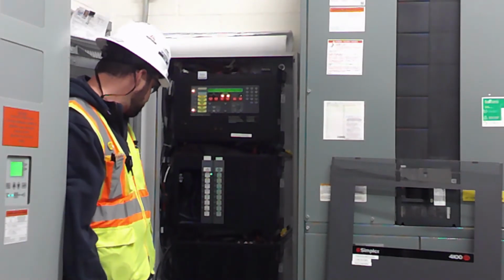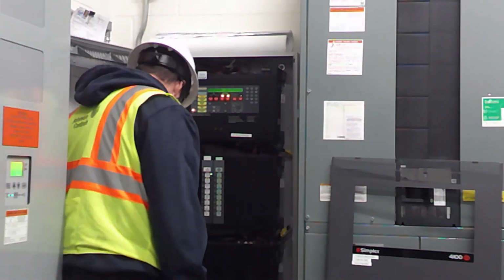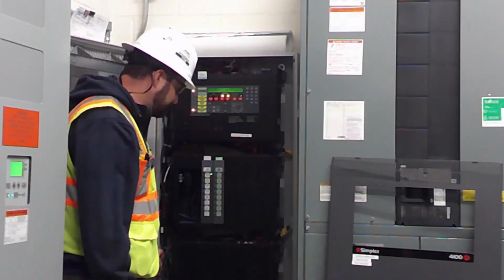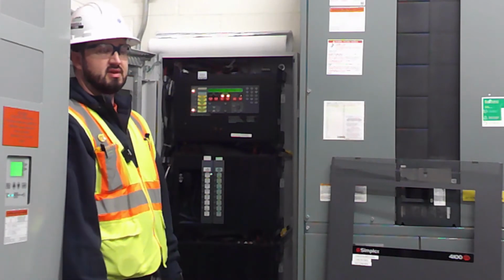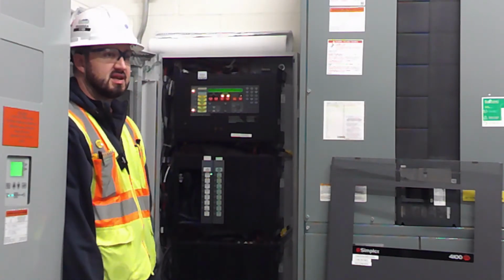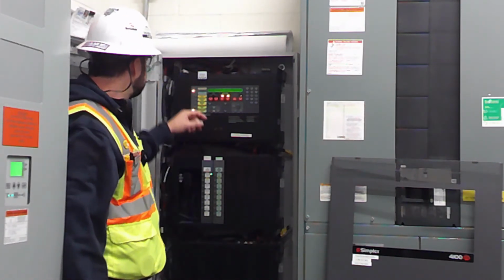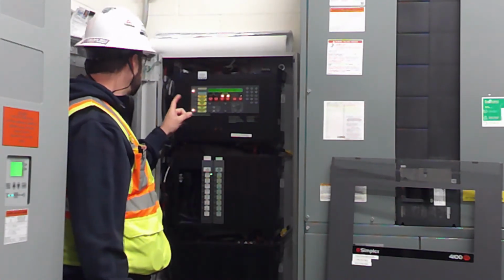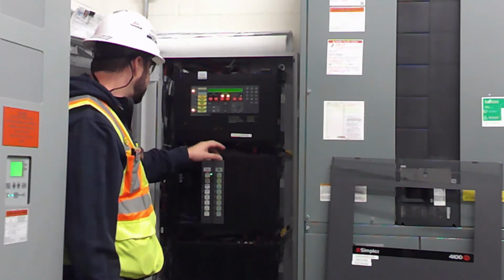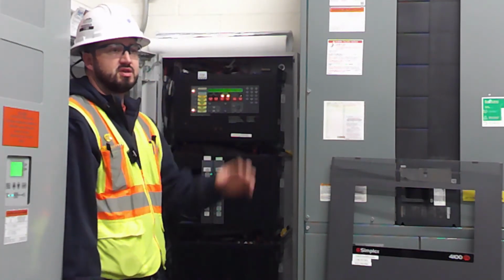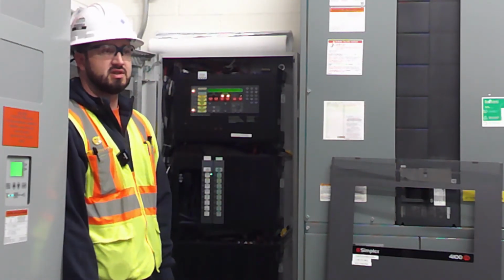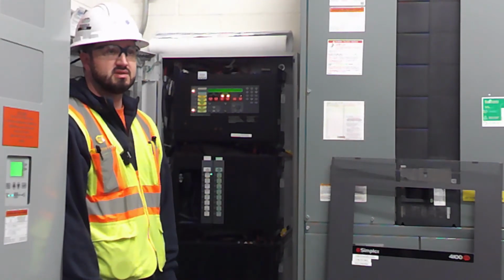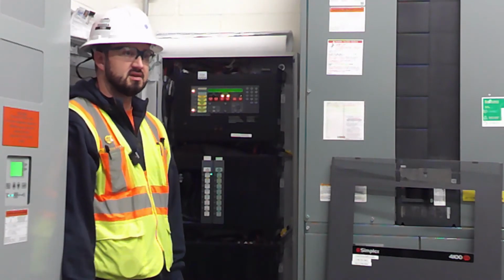Everything runs down from the ground right there, under the gutter. Down in the gutter, a lot of it is the thick, underground UF rated cable for everything they pulled down in the slabs and things like that. Most of this panel is all underground rated. I think there's very few that are actually just your standard THHN. But as you go around to other panels, there's not as much underground, so you'll see more of the standard red 18.2s and 16.2s and things like that.